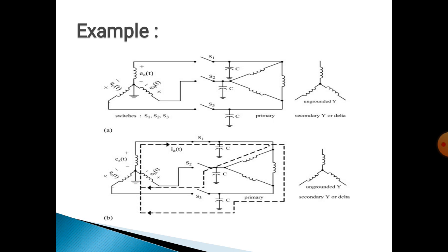We have considered the possibility of ferroresonant overvoltages on Y delta transformer banks during single phase switching as a function of transformer size and length of the cable. These are the main examples of ferroresonance condition.